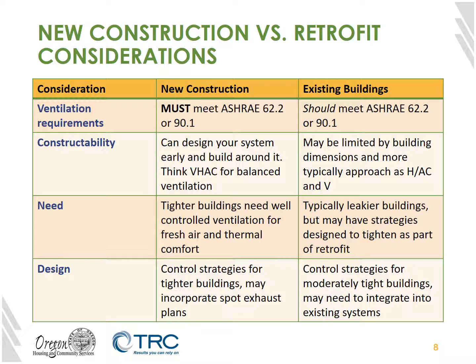Beyond that, there's what we sometimes refer to as the constructability. And it's going to come down to how we design these. We use the term HVAC a lot, which stands for heating, ventilation, and air conditioning, or as some installers refer to it, heating, venting, and cooling. When we put in something like a balanced ventilation system in new construction, we can actually rearrange those and think VHAC. We can put ventilation before heating and cooling because it will actually impact the loads that need to be met by the heating and cooling equipment. When we look at existing buildings, we may be limited by the building's dimensions and some of the existing equipment that's already there. So we tend to think of them as two separate approaches, heating and cooling and V for ventilation.